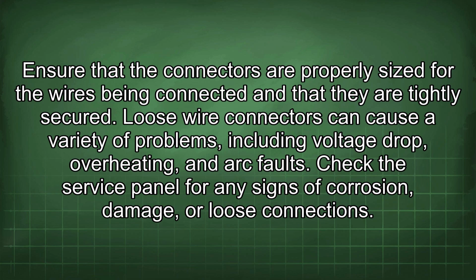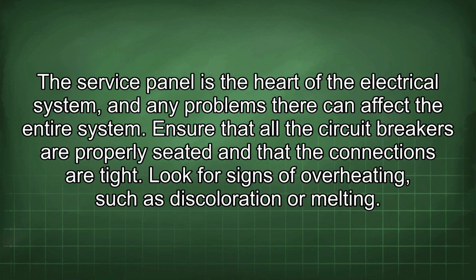Check the service panel for any signs of corrosion, damage, or loose connections. The service panel is the heart of the electrical system, and any problems there can affect the entire system. Ensure that all the circuit breakers are properly seated and that the connections are tight. Look for signs of overheating, such as discoloration or melting.